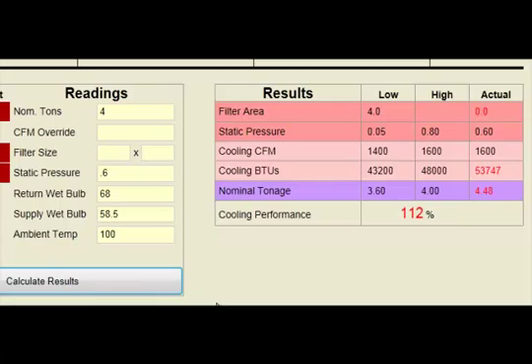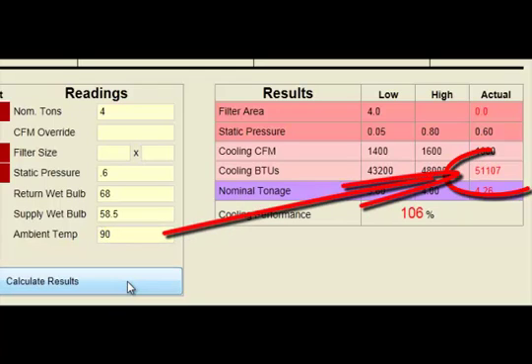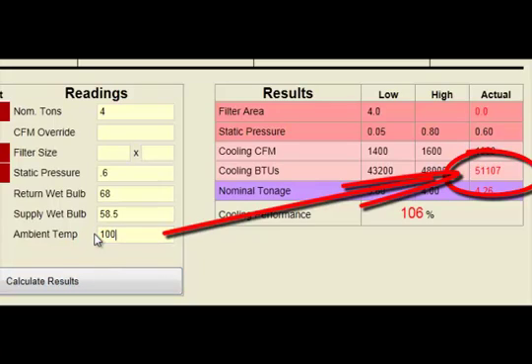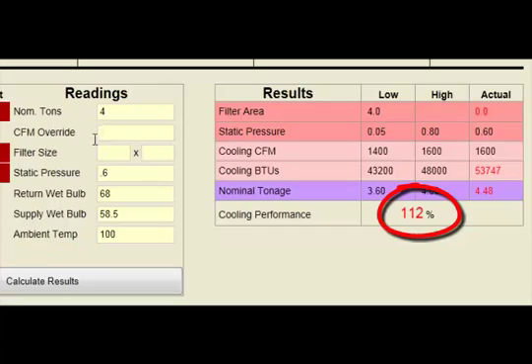There is an additional practical use for the CFM Override feature. Since Total Performance Diagnostics employs a temperature-correcting algorithm that represents cooling BTUs at rated capacity, any capacity reading that exceeds 100% of nominal tons is, in reality, an impossible real-world condition.